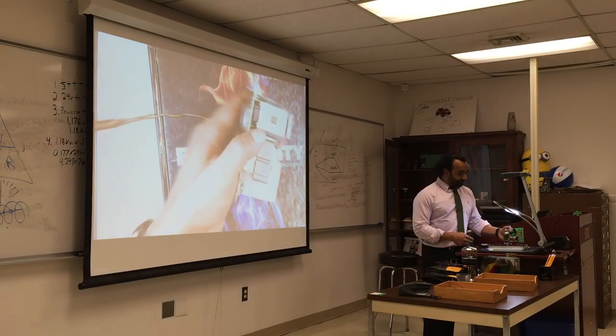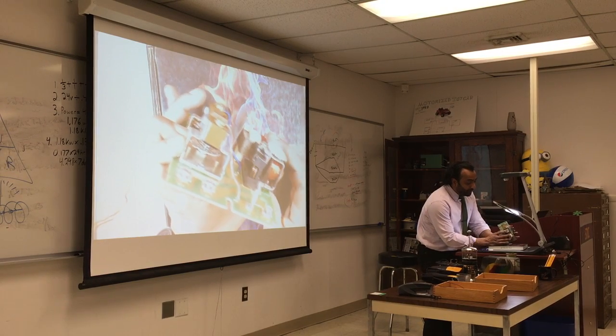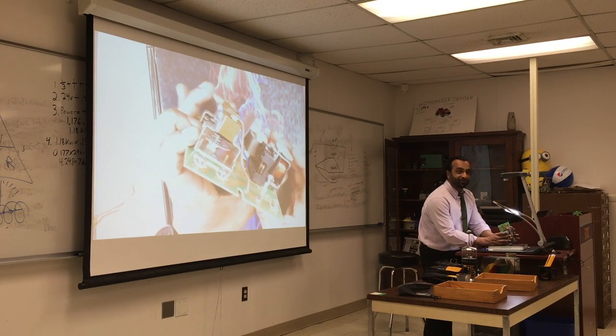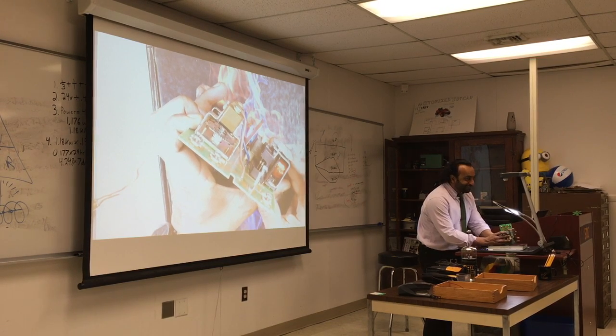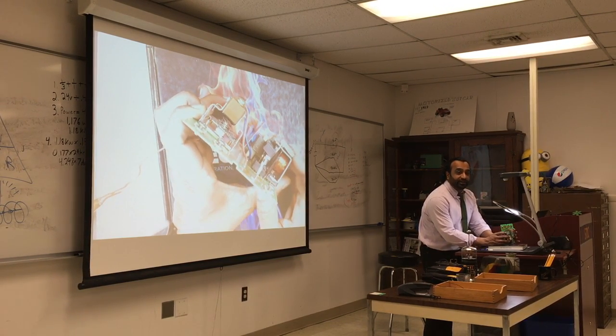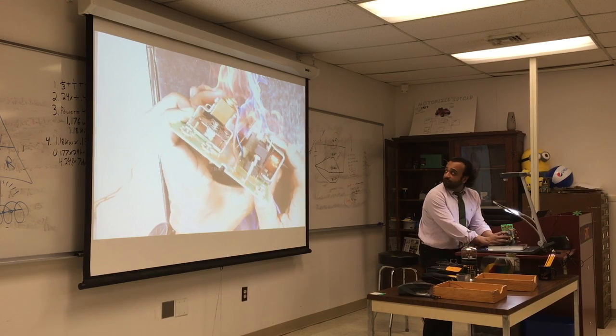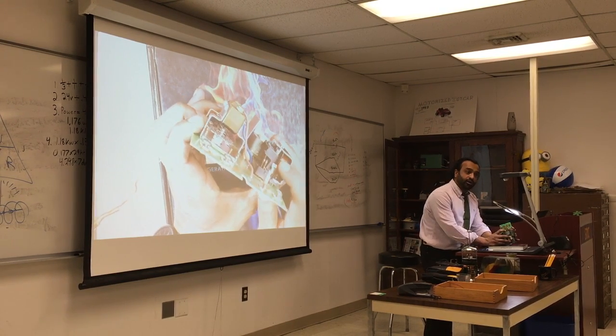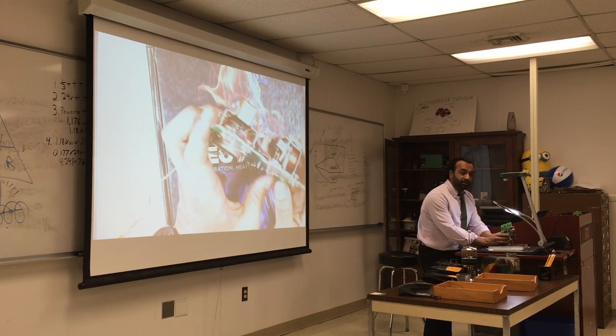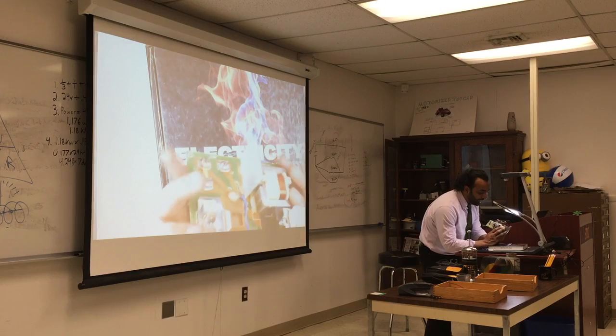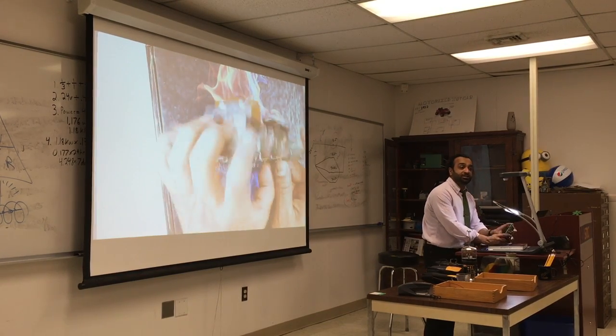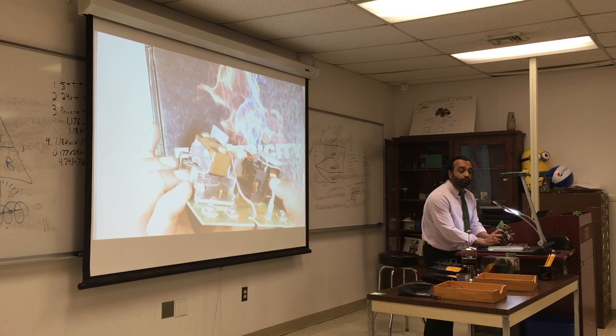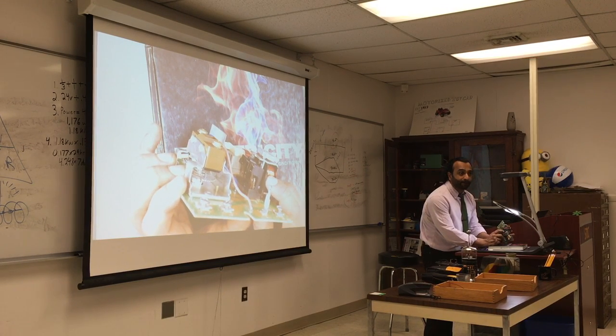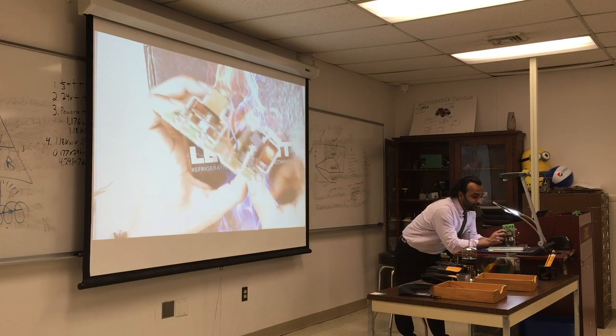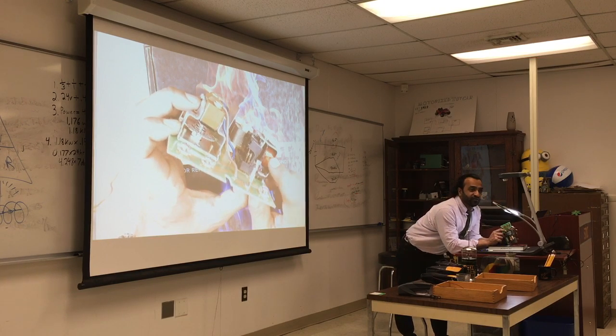If we look at this coil here, this coil is creating a magnet to pull in those contacts. So I can test this coil and see if it's functioning by testing the resistance inside. Usually I can look up the model number and see what resistance I'm supposed to be getting, because sometimes it's functioning halfway, like half those coils is burnt or fused together. If you look very closely, why do you think this is very red?